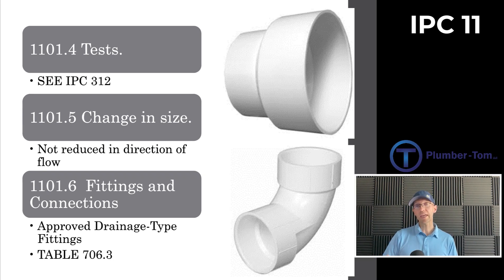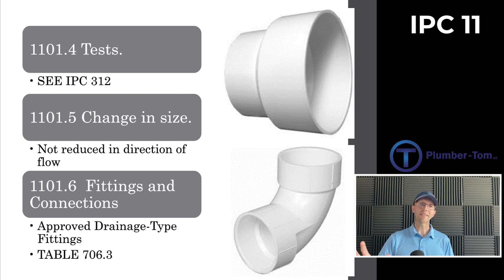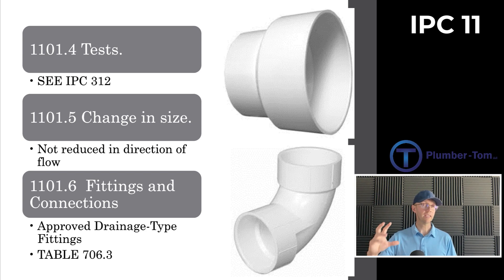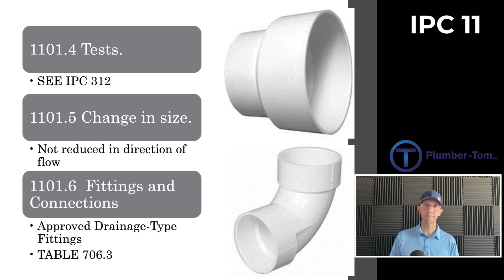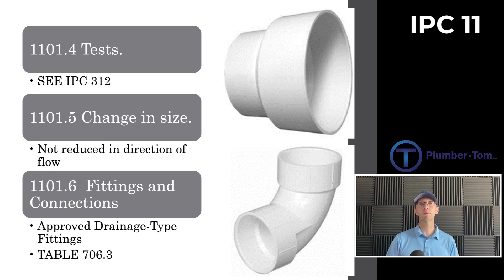1101.5 speaks to the change of pipe size. Just like any other drainage system, we are told not to reduce the pipe size in the direction of flow — this could cause a possible blockage. When a size gets bigger, it remains bigger; we never shrink as we go. 1101.6 covers fittings and connections, stating we'll use the same type of fittings and pipe as in Chapter 7, referring us to Table 706.3.